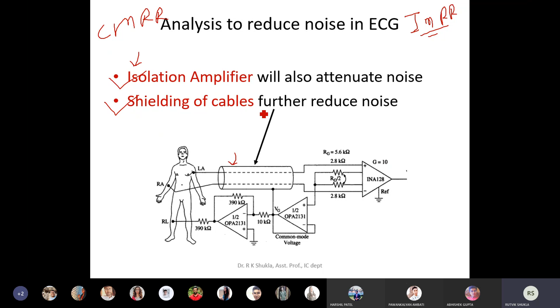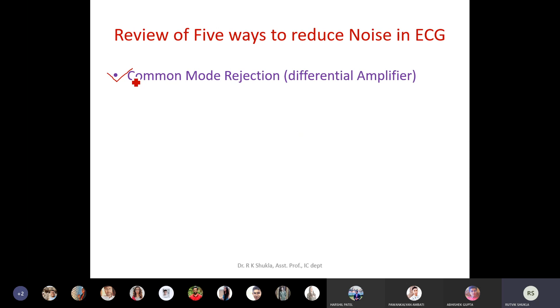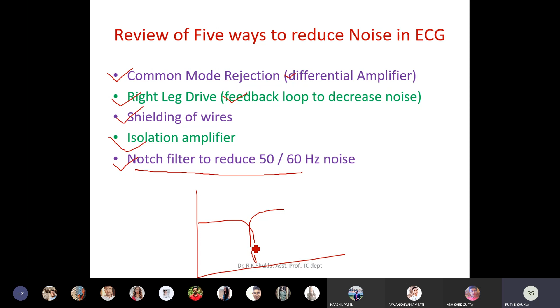So if we review the different ways by which we can reduce the noise in ECGs: first, we are using the common mode rejection capability of a differential amplifier. Second, we are using a right leg driver in which we send part of the input back to the patient. Third, we are using shielding of wire. Fourth, we are using the isolation amplifier. And in addition to this, we are also using one more mechanism, which is called the notch filter. As we have seen, a notch filter is like this. It has the capability to reduce or reject a particular component. If we are using a 50 Hz notch, it can cancel that 50 Hz component, or if we are using a 60 Hz notch, it can cancel the 60 Hz component.